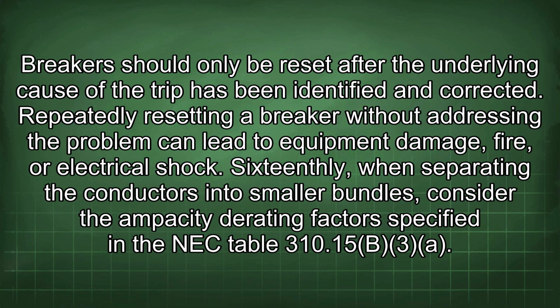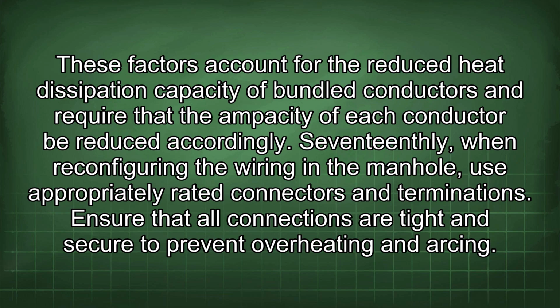16thly, when separating the conductors into smaller bundles, consider the ampacity derating factor specified in the NEC Table 310.15(B)(3). These factors account for the reduced heat dissipation capacity of bundled conductors and require that the ampacity of each conductor be reduced accordingly. 17thly, when reconfiguring the wiring in the manhole, use appropriately rated connectors and terminations. Ensure that all connections are tight and secure to prevent overheating and arcing.